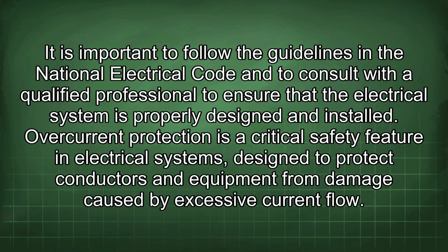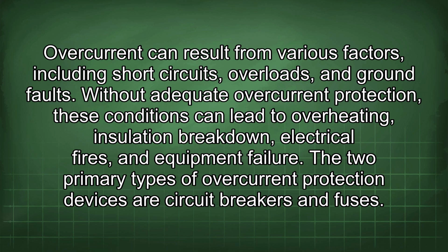Overcurrent protection is a critical safety feature in electrical systems, designed to protect conductors and equipment from damage caused by excessive current flow. Overcurrent can result from various factors, including short circuits, overloads, and ground faults. Without adequate overcurrent protection, these conditions can lead to overheating, insulation breakdown, electrical fires, and equipment failure.